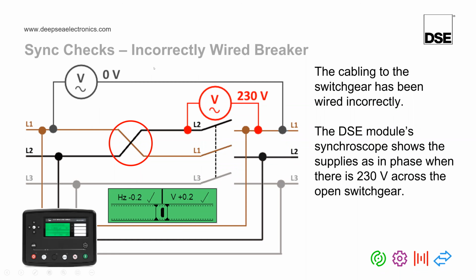So in this case, the DeepSea module is sensing 0 volts. Therefore, it is showing on the display, everything is okay, everything is in sync. And then across the open breaker, you would actually see 230 volts. At this point, the DeepSea module would request the breaker to close and everything would end badly.